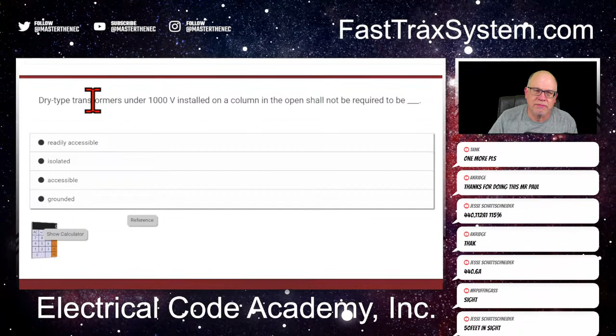Hopefully you know, okay? Oh, and by the way, the 2023 edition now defines what a transformer is. We all know a transformer is a separately derived system, but not all transformers are separately derived systems. For example, an autotransformer is not a separately derived system. Okay, so it was important in the 2023 to add a definition of transformer. So that's what you've got. You've got a new definition. All right, but we know transformers are in what article? 450. So let's go to 450.